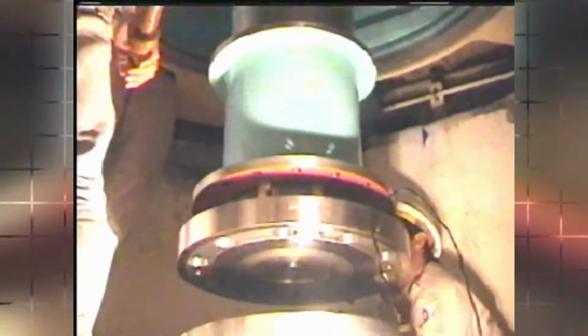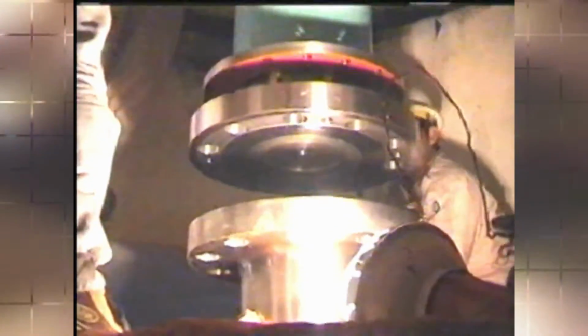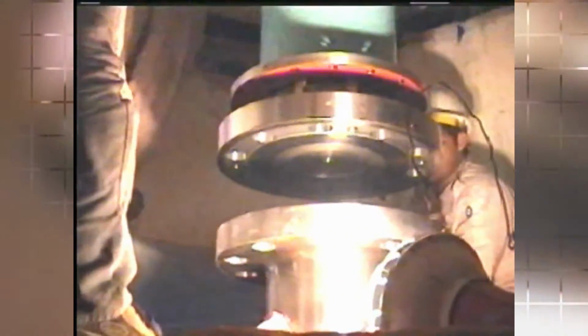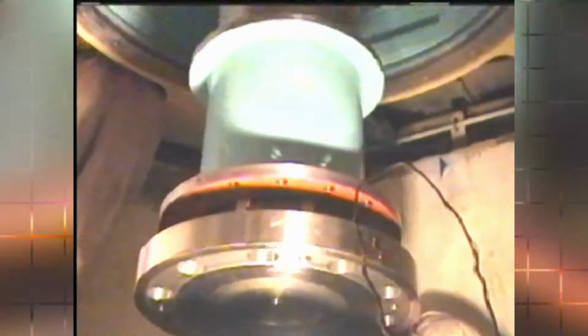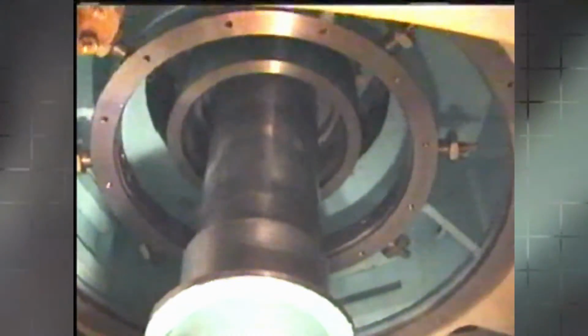The brakes are designed to serve as hydraulic jacks to lift the generator rotor and rotating parts of the turbine a sufficient distance to provide for removal or adjustment of the thrust bearings, and all affected parts of the generator are designed to provide for vertical movements of this amount without the necessity of any disassembly of such parts.